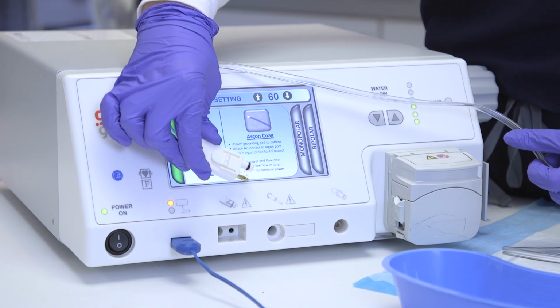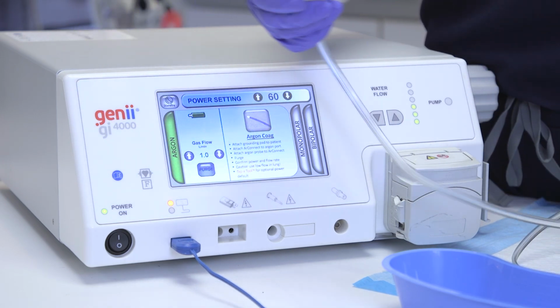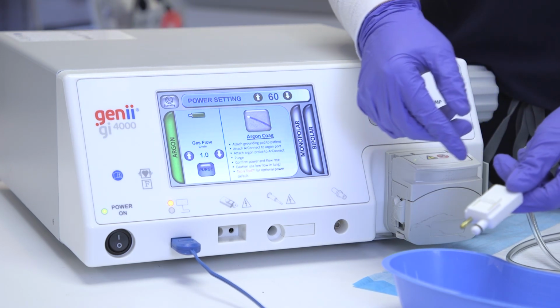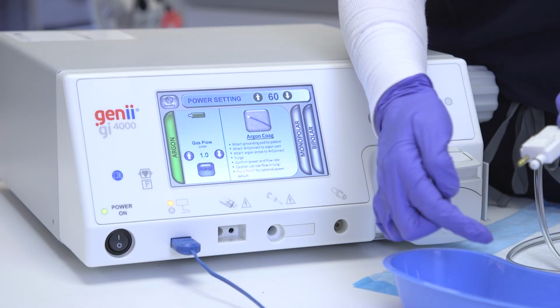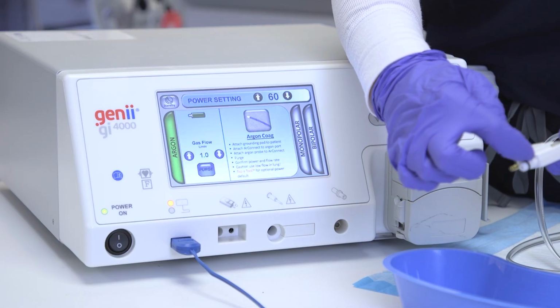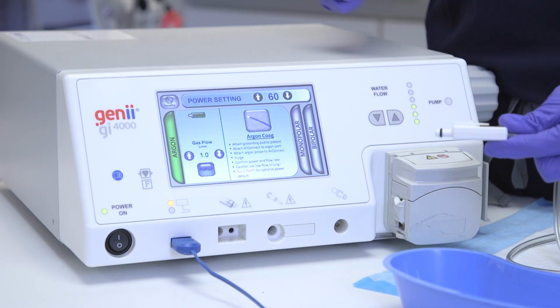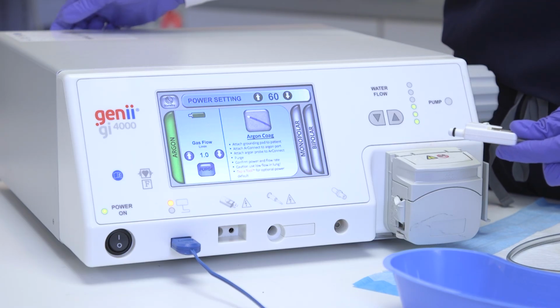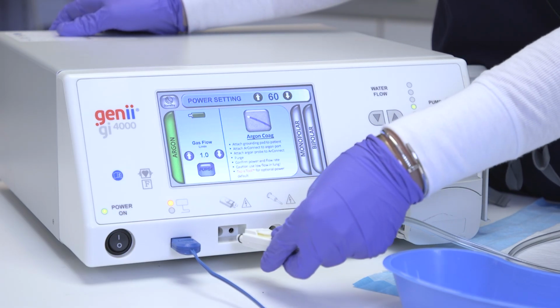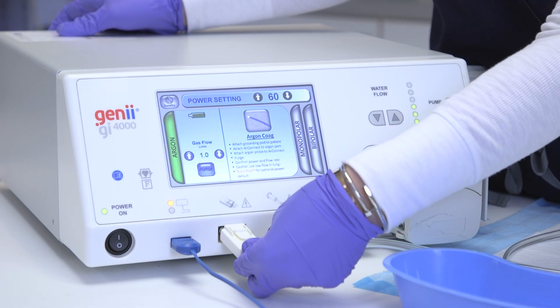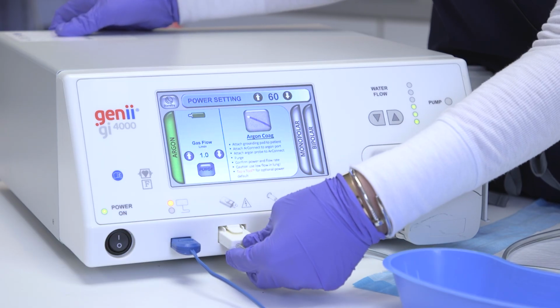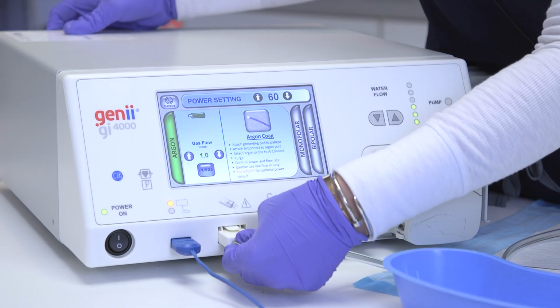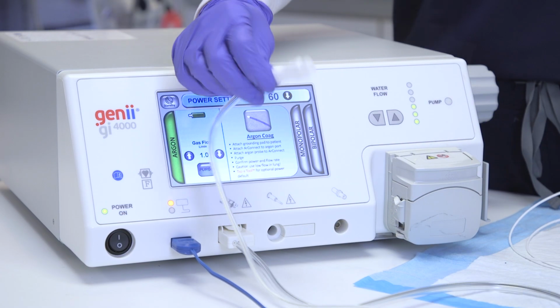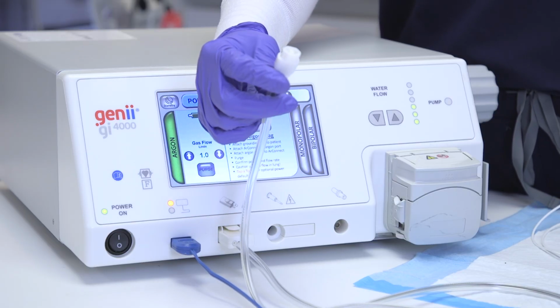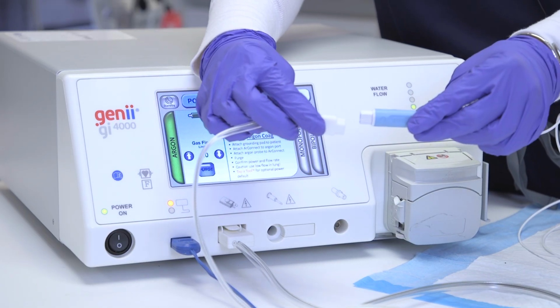You'll notice the Arc Connect icon here. For easiest insertion, you'll want to take the Arc Connect with a gloved hand into a bit of water and dab it around the O-ring for easier insertion. You'll also want to place your hand on the back of the gi4000 unit for leverage. When installing the Arc Connect, you'll want to make sure that it clicks into place. The other end of your Arc Connect plugs directly into your standard Argon probe connector.